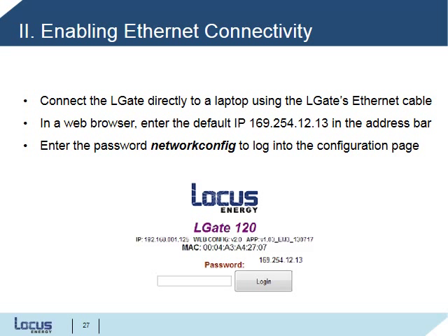To enable the Ethernet connection, you'll need to log in to the LGate directly using a laptop and the LGate's Ethernet cable. After setting this up, you'll open a web browser and enter the default IP address 169.254.12.13 in the address bar. Enter the password networkconfig, all lowercase, to log in to the configuration page.